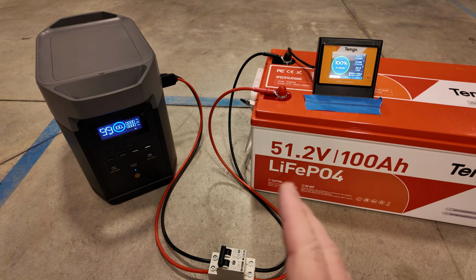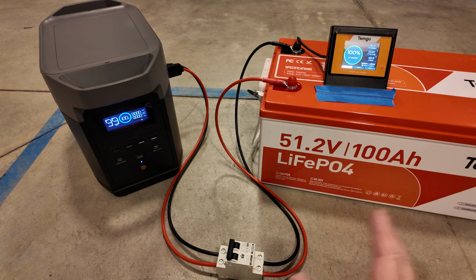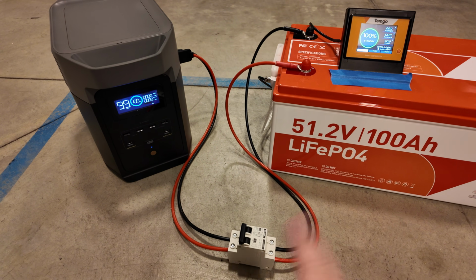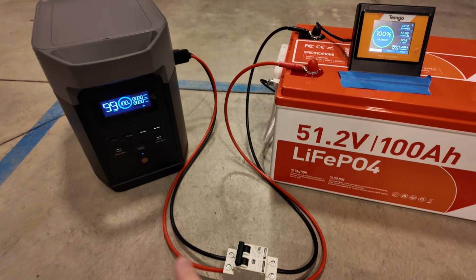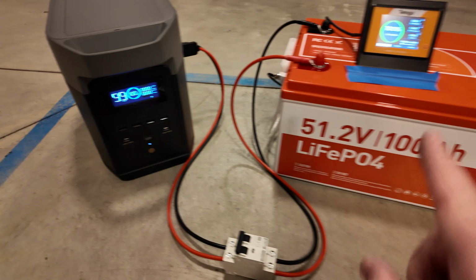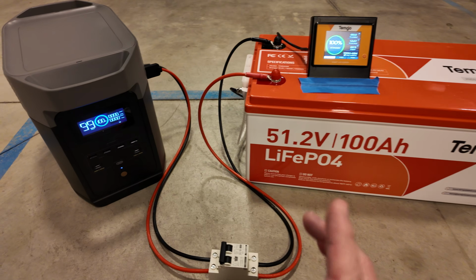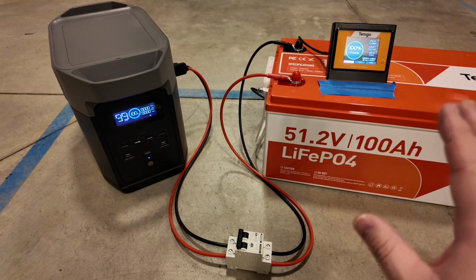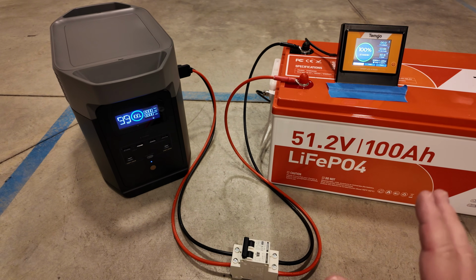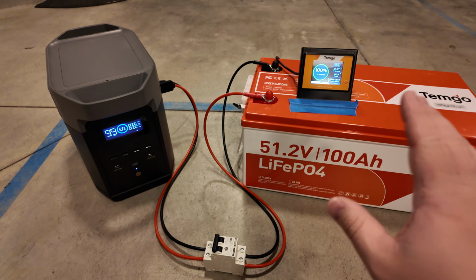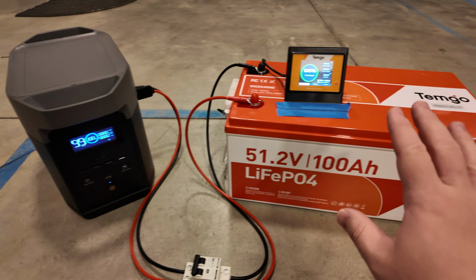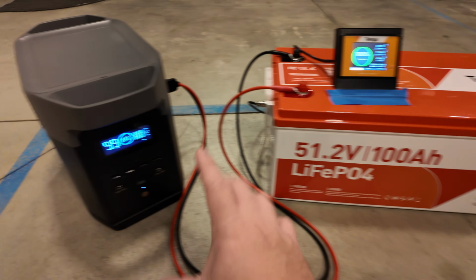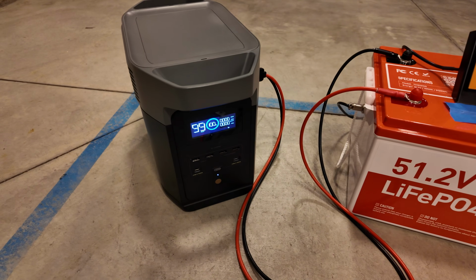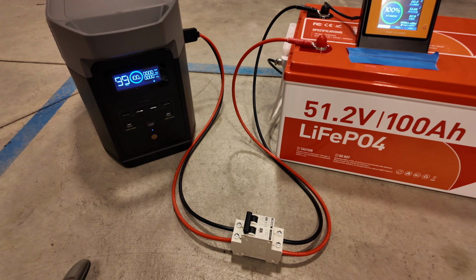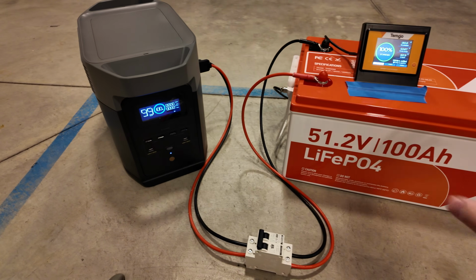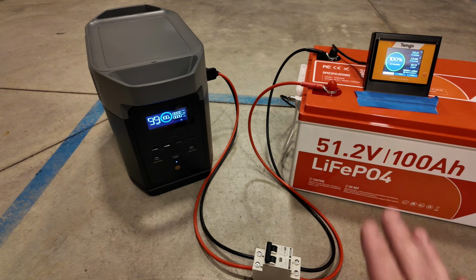Another important factor you've got to remember before just plugging stuff in and flipping switches: there's no communication between this unit and this external battery. So you need to be the one that ensures they are identical in state of charge. Because what you don't want is this battery fully charged and the other at, say, 20% state of charge, and you flip your switch and suddenly there's a big voltage differential as well as state of charge differential.